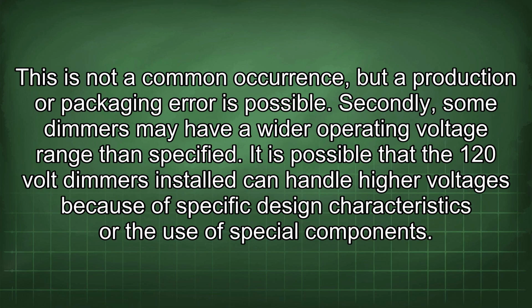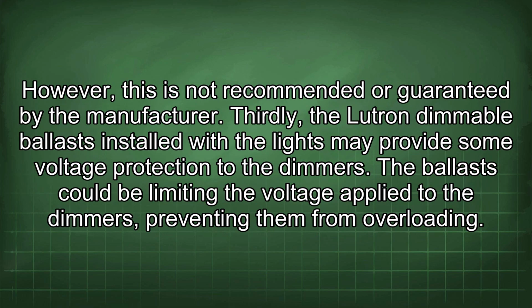Secondly, some dimmers may have a wider operating voltage range than specified. It is possible that the 120-volt dimmers installed can handle higher voltages because of specific design characteristics or the use of special components. However, this is not recommended or guaranteed by the manufacturer. Thirdly, the Lutron dimmable ballasts installed with the lights may provide some voltage protection to the dimmers. The ballast could be limiting the voltage applied to the dimmers, preventing them from overloading.